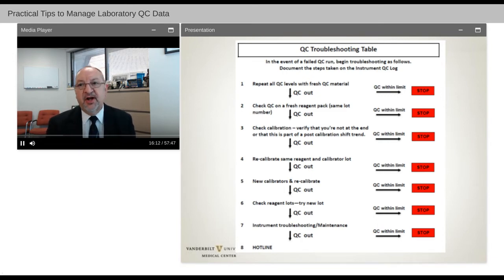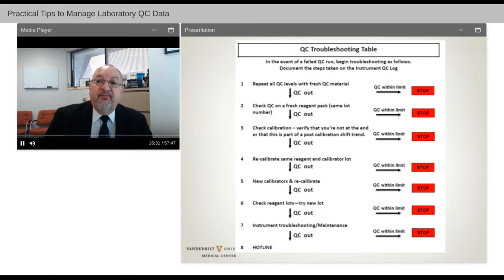If not, we can go on and look to a fresh package of reagent from the same lot. We should then be checking for calibration. When was the last time the assay was calibrated? Is it very close to outdating or has the calibration expired? We also want to look, after calibration, maybe changing reagent lots or checking for other calibrator lots before we go on to looking at instrument maintenance, troubleshooting the analyzer as parts and calling the manufacturer in for repairs. So this is a general overview of how to approach troubleshooting out of range QC.